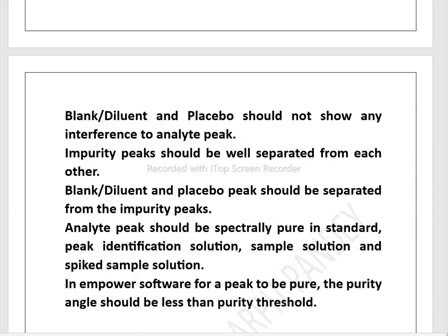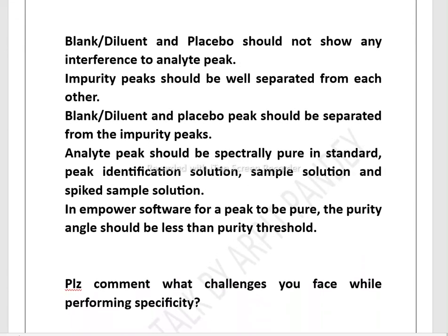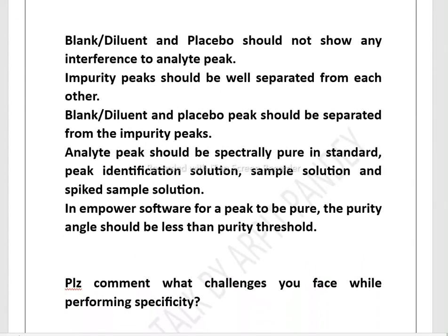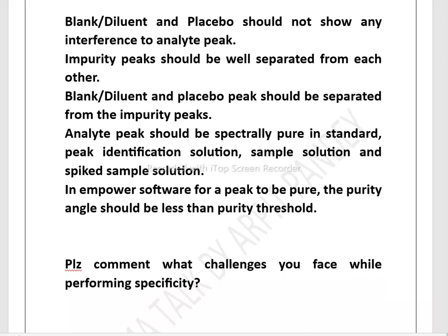Regarding peak purity measurement — in Empower software, for a peak to be considered pure, the purity angle should be less than the purity threshold. If the purity angle is less than the purity threshold, it means that your peak is pure and homogeneous. This is what specificity means in method validation. I will provide more detail about peak purity in my next video.